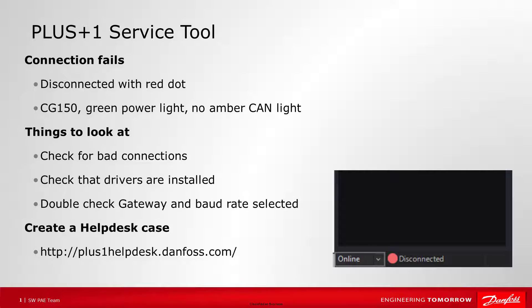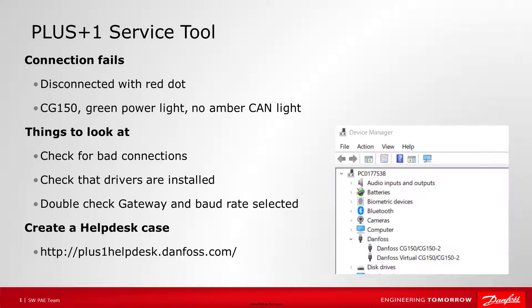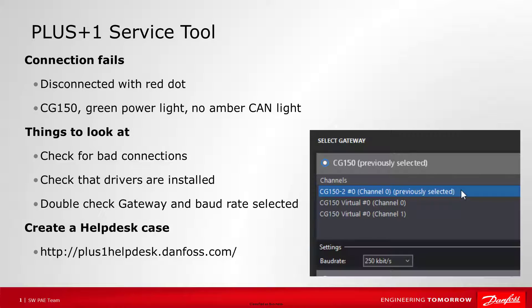If the connection still fails, with the service tool saying disconnected at the bottom with a red dot, and the CG150 has a green power light but no amber CAN light, check for bad connections and make sure the Danfoss CG150 driver is installed. When you go to select the CG150 in the Communications menu, be sure the correct CG150 and baud rate is selected. You can also create a help desk case at plusonehelpdesk.danfoss.com. Be sure to let us know what version of service tool and hardware you are working with.